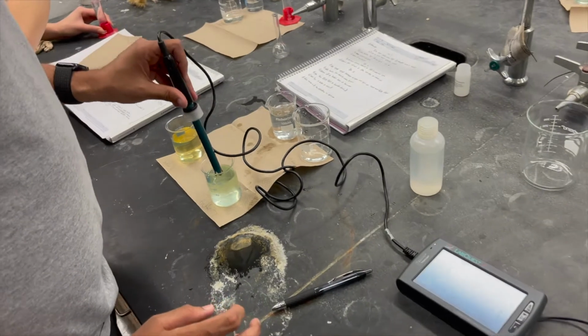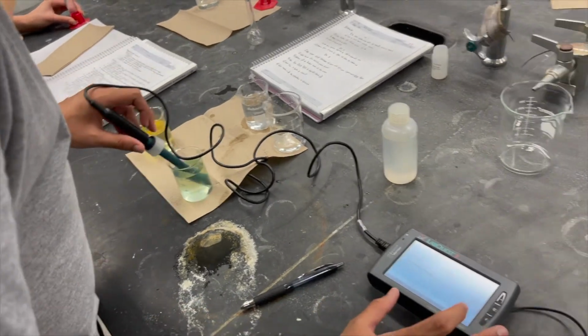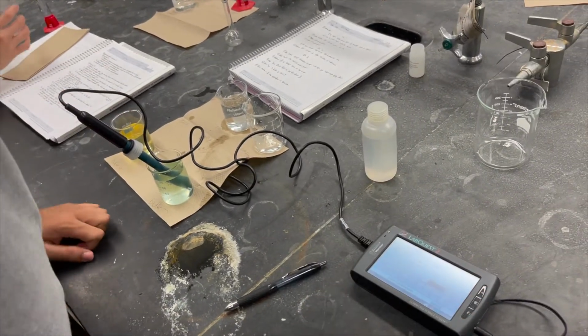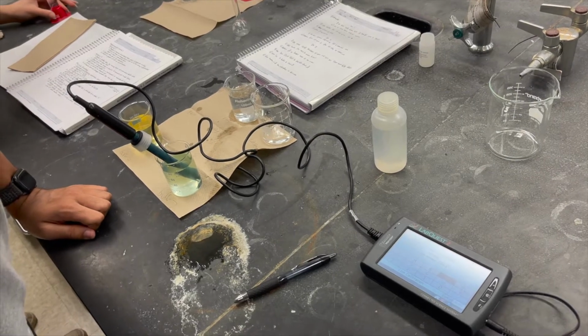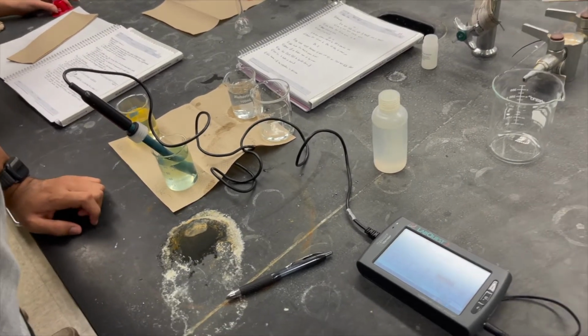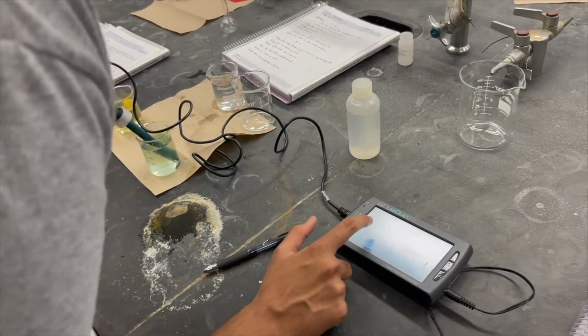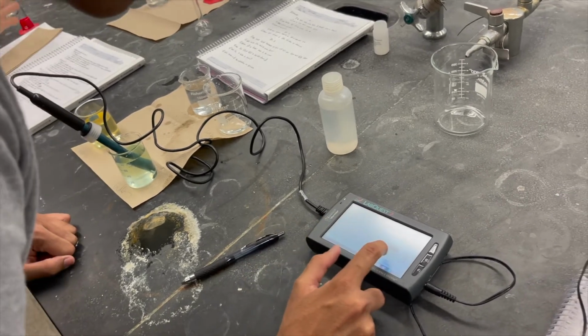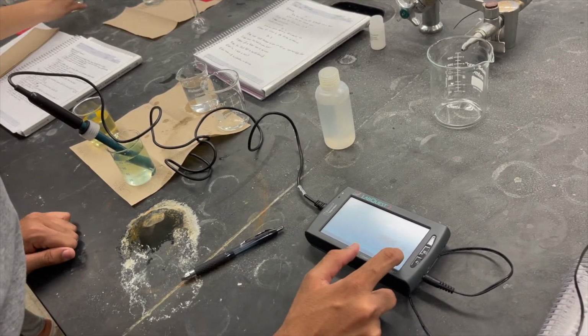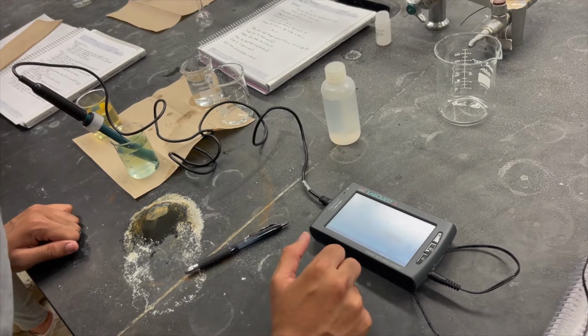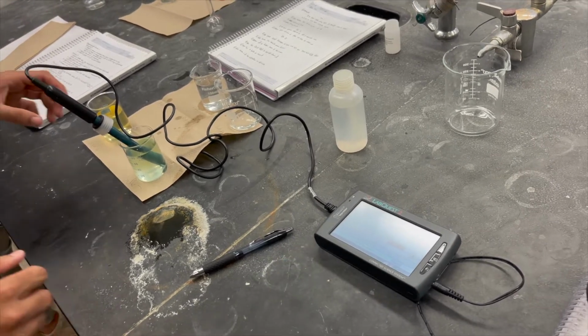by using the display. Press the button labeled Sensors, then Calibration, then CH1 pH1, Calibrate Now, and make sure that the 1-point calibration is not selected. Then, wait for the voltage to level out and then enter in pH 7.